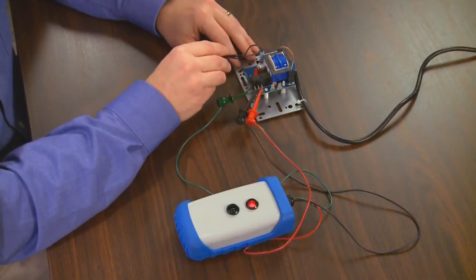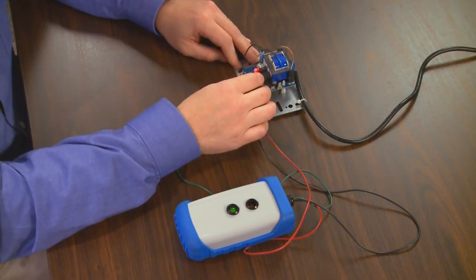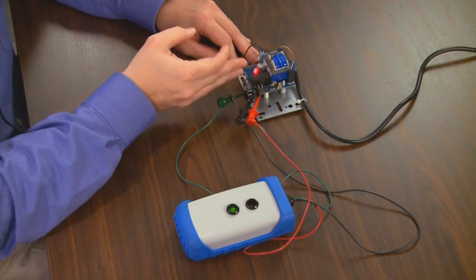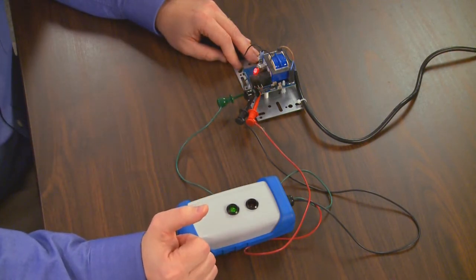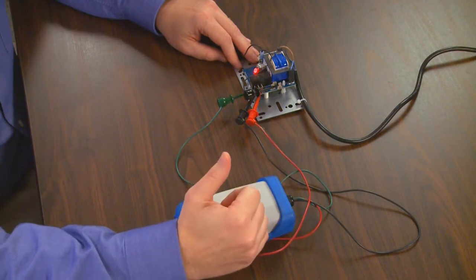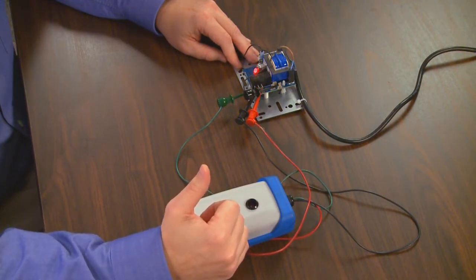Now in a single level service direct mode when water hits the high probe LED comes on relay is energized you notice that the lights have changed state the normally closed contact becomes open the normally open contact is now closed.